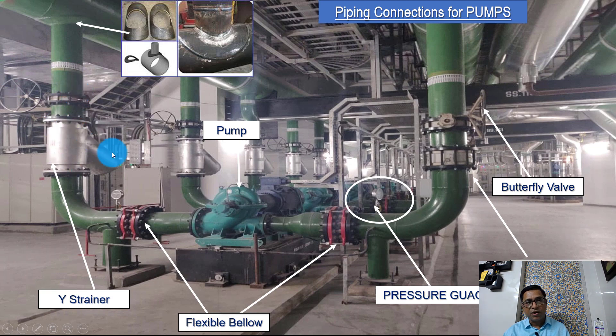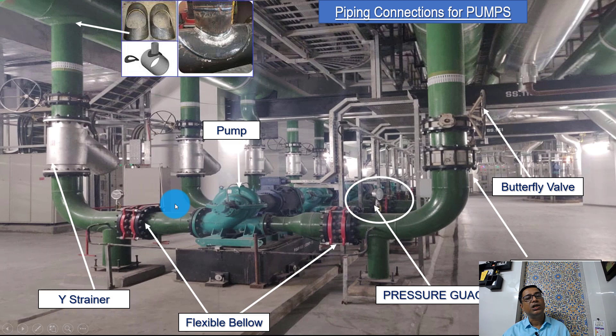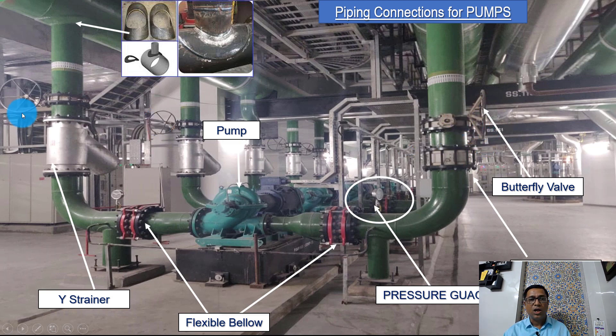Then we have a Y-strainer. From here we can clean the Y-strainer. Then we have a flexible bellow, a pressure gauge. The test point is not here, but it is required wherever the BMS connection is needed. We have flexible bellows over here and a pressure gauge again. Then we have an NRV on the discharge side and then butterfly valve. So these are the two isolating valves.